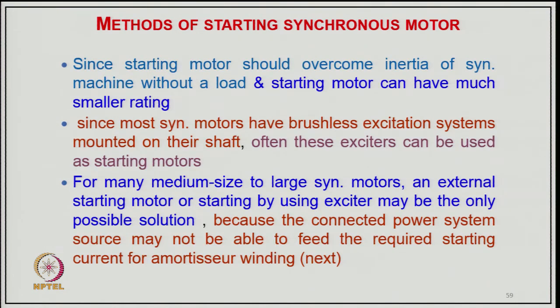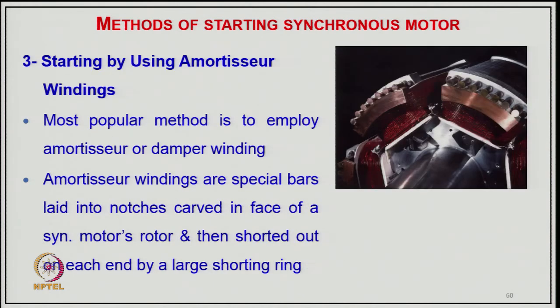Since the starting motor only has to overcome the inertia of the synchronous machine without a load, it can have a much smaller rating, and since most synchronous motors have a brushless excitation system mounted on their shaft, often these exciters can be used as a starting motor. For many medium to large synchronous motors, an external starting motor may be the only possible solution, because the connected power system may not be able to feed the required starting current. And this is the third method, starting by the damper winding.